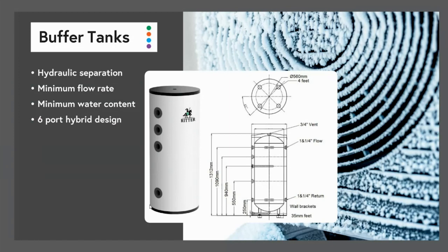So good system design with heat pumps is essential, and buffer tanks reduce the likelihood of any flow-related issues, because the heat pump can circulate the water from itself to the buffer tank and back very, very easily, because the pressure drop is very low. And then the minimum water content, which is required for the defrosting cycle, which we talked about on the previous slide, that's stored in the buffer tank.